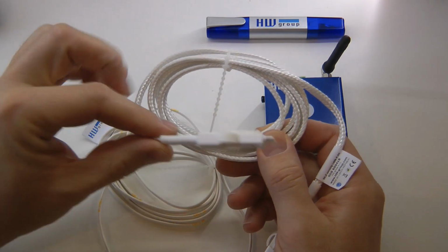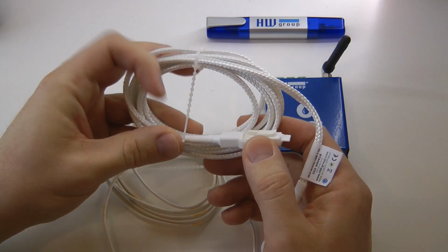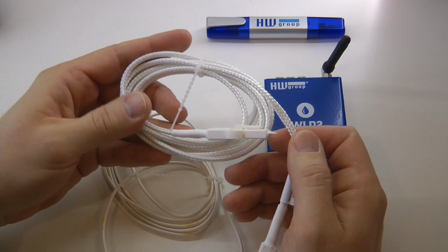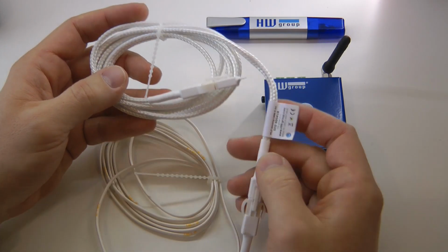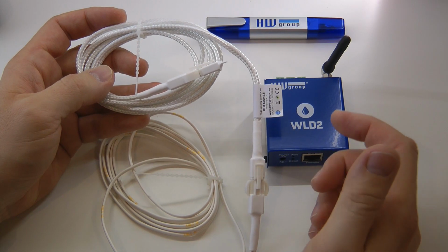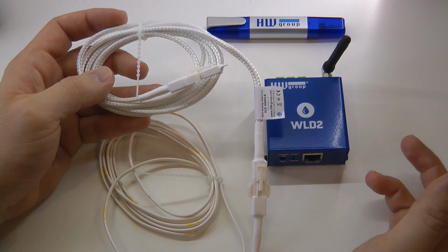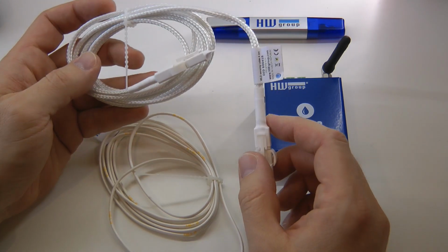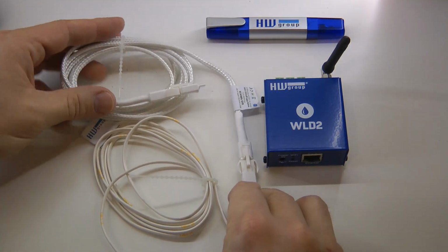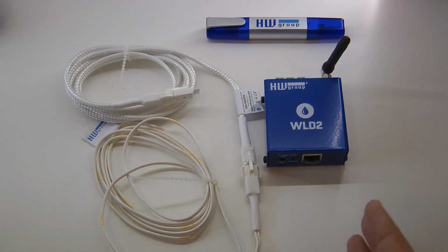It uses some sort of chemical process, because in the presence of water, the conductivity of this wire changes, and that's what the device is able to detect. So it detects whether there is a presence of water. It's going to be a binary value, so either water is detected or water is not detected, and it wouldn't be able to tell you at what point within the wire the water is detected. It basically just gives you a true or a false alarm.